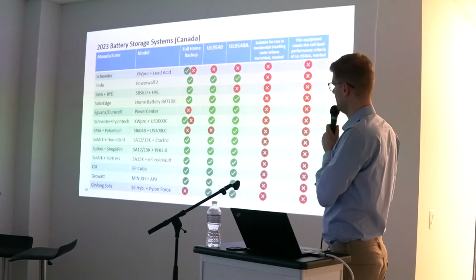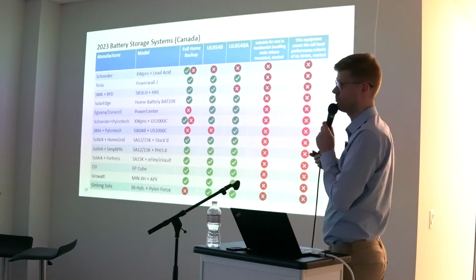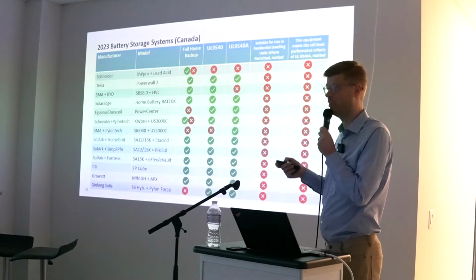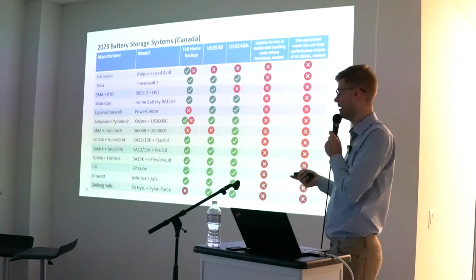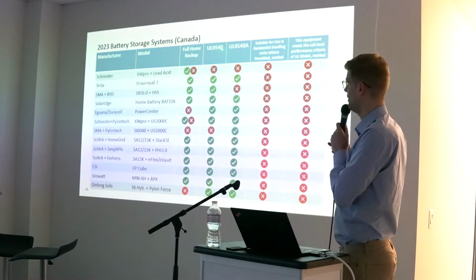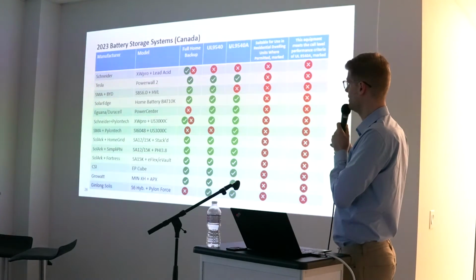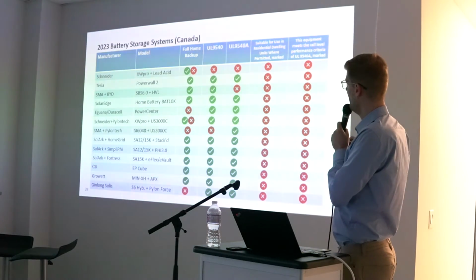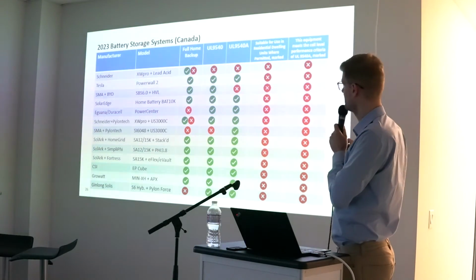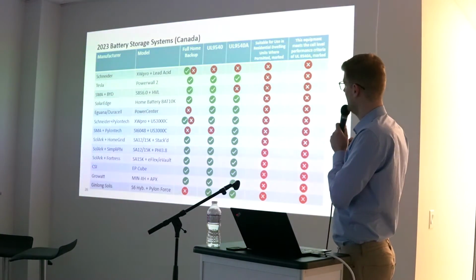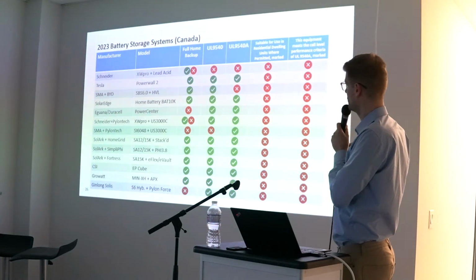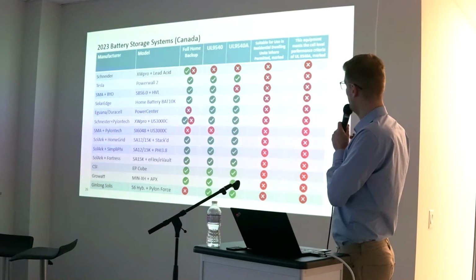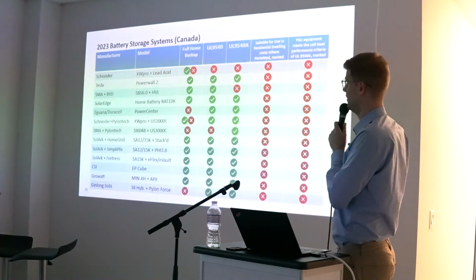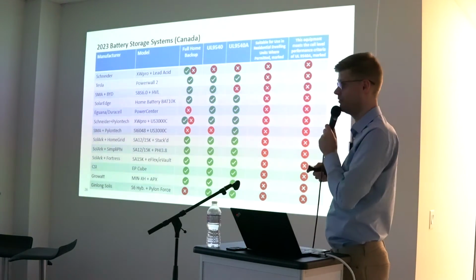You see here in that column the full home backup, because most customers today prefer if the entire home is on backup. We have the UL9540 system certification. We have the fire propagation testing under 9540A. And then we have the marking and the listing on the type label, if it says suitable for use in residential dwelling units where permitted, and/or if this equipment meets the cell level performance criteria of UL9540A.